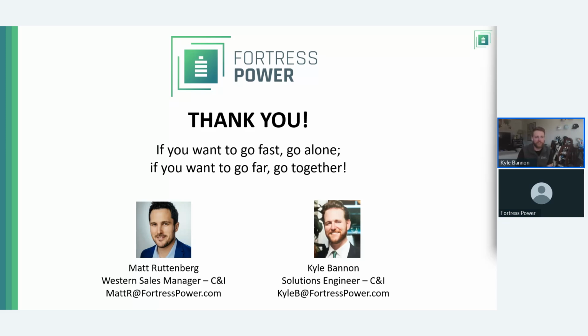Is the inverter 3-phase, or can it work with 3 phases individually? Technically, yes, you can pull individual phases from the 3-phase output that the system outputs. But you really need to balance your phases properly, because if you throw one phase out of whack compared to the other two, the system will fault. So you could build your own split phase or single phase system off of this, but it comes down to balancing the loads properly so it doesn't fault out the inverter.